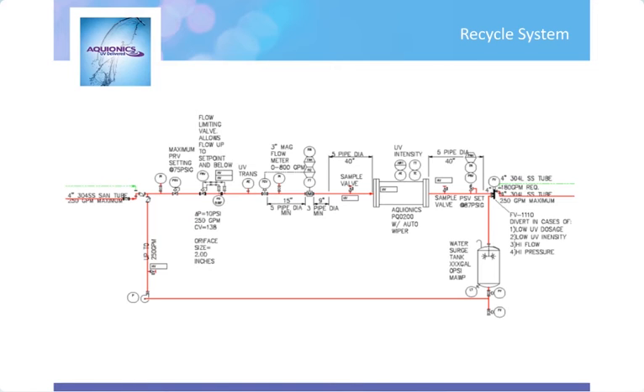We have also designed, I haven't shown it, but basically a pasteurized equivalent water system that has a storage tank. Again, this is very useful when high rates of flow are needed for a short period of time. We can build a surge to balance the pasteurized equivalent water supply with the usage and keep the UV system basically sized for the average rather than for an infrequent peak load.